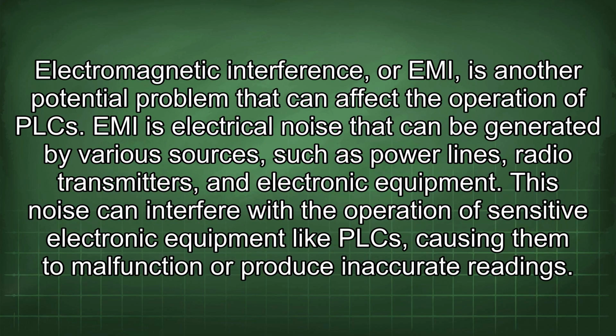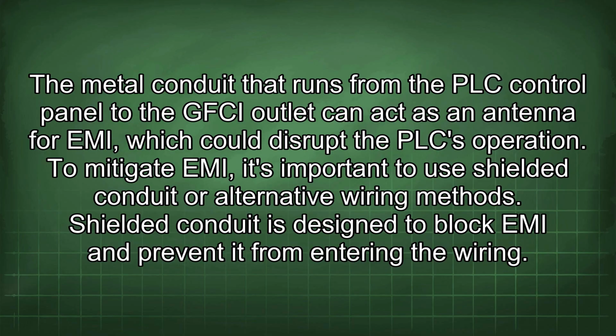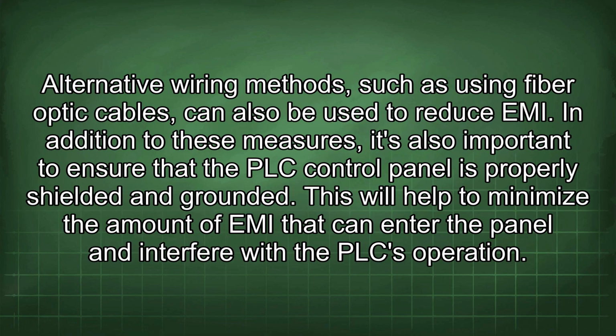The electromagnetic interference, or EMI, is another potential problem that can affect the operation of PLC. EMI is electrical noise that can be generated by various sources such as power lines, radio transmitters, and electronic equipment. This noise can interfere with the operation of sensitive electronic equipment like PLC, causing them to malfunction or produce inaccurate readings. The metal conduit that runs from the PLC control panel to the GFCI outlet can act as an antenna for EMI, which could disrupt the PLC operation. To mitigate EMI, it's important to use shielded conduit or alternative wiring methods. Shielded conduit is designed to block EMI and prevent it from entering the wiring. Alternative wiring methods, such as using fiber optic cables, can also be used to reduce EMI. In addition to these measures, it's also important to ensure that the PLC control panel is properly shielded and grounded. This will help to minimize the amount of EMI that can enter the panel and interfere with the PLC operation.